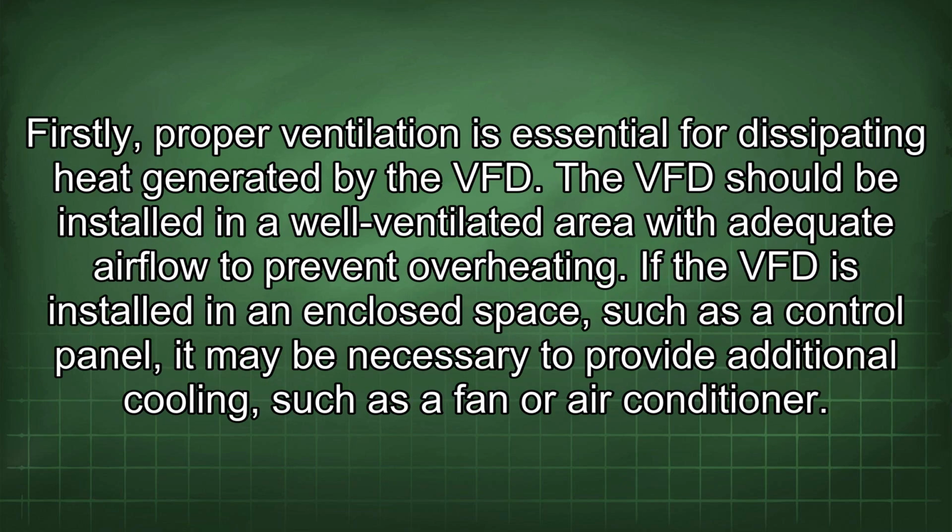Firstly, proper ventilation is essential for dissipating heat generated by the VFD. The VFD should be installed in a well-ventilated area with adequate airflow to prevent overheating. If the VFD is installed in an enclosed space, such as a control panel, it may be necessary to provide additional cooling, such as a fan or air conditioner.